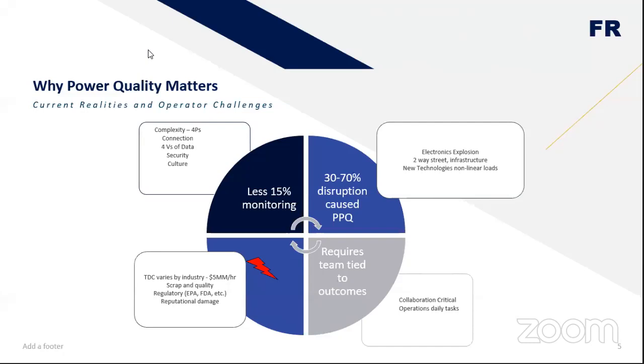We also know it's a two-way power street on the plant floor. Some new technologies with positive intended consequences, like slowing down your motor drives to decrease energy cost and consumption, create nonlinear loads at the same time. So you've got variable frequency drives, LED lighting, and different sources of potential poor power quality.